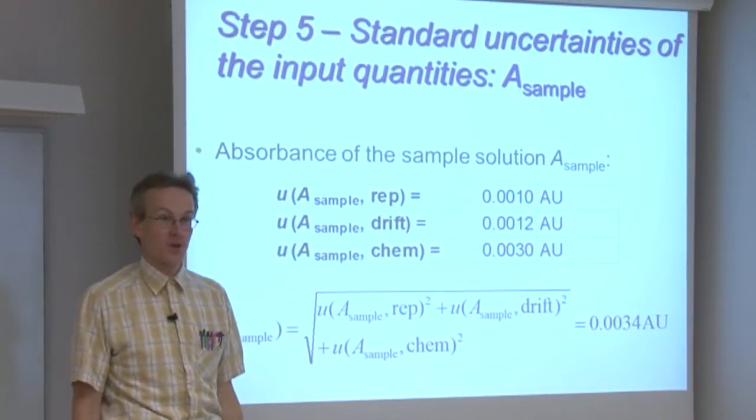The drift uncertainty can likewise be determined in the laboratory, but also it sometimes can be found in the documentation of the spectrophotometer. These values correspond to quite safe estimates for contemporary, normal, usual routine spectrophotometers.